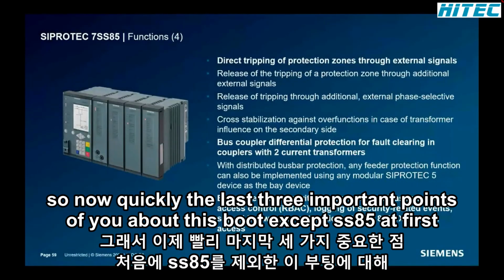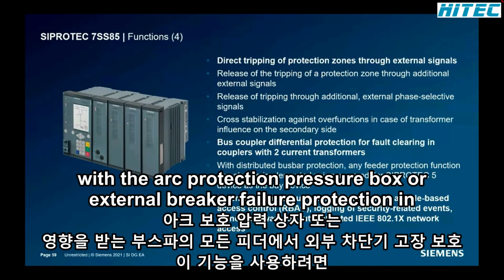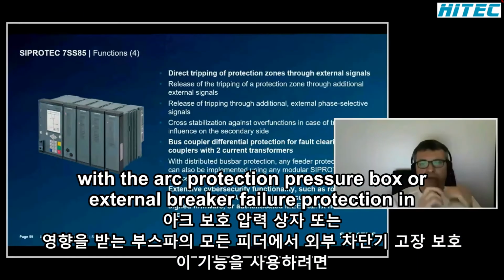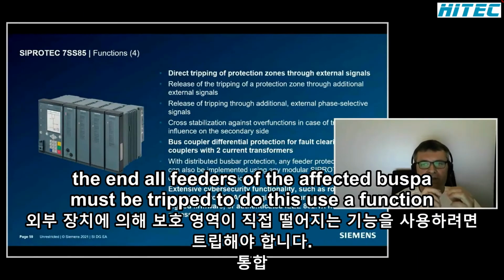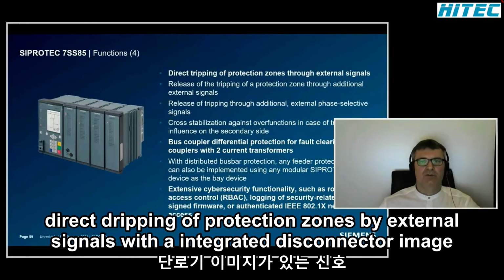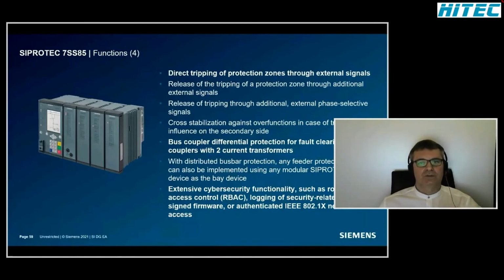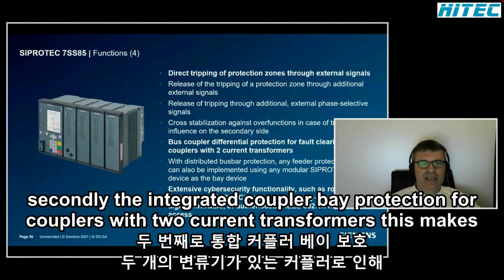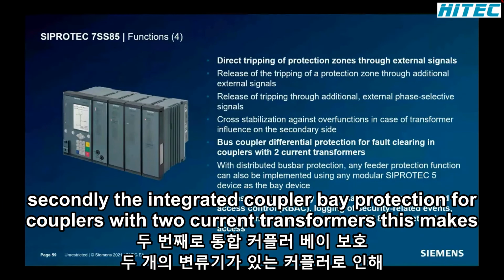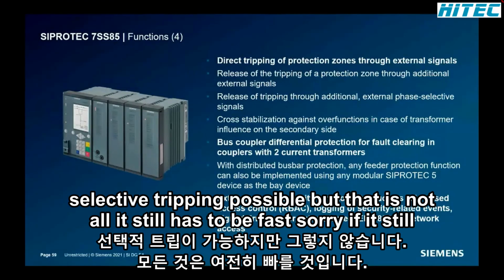So now quickly, the last three important points of view about the SIPROTEC 7SS85. At first, whether arc protection, pressure box, or external breaker failure protection, in the end, all feeders of the affected busbar must be tripped. To do this, use the function direct tripping of protection zones by external signals with the integrated disconnector image. Secondly, the integrated coupler bay protection for couplers with two current transformers. This makes selective tripping possible, but that is not all. It still has to be fast.